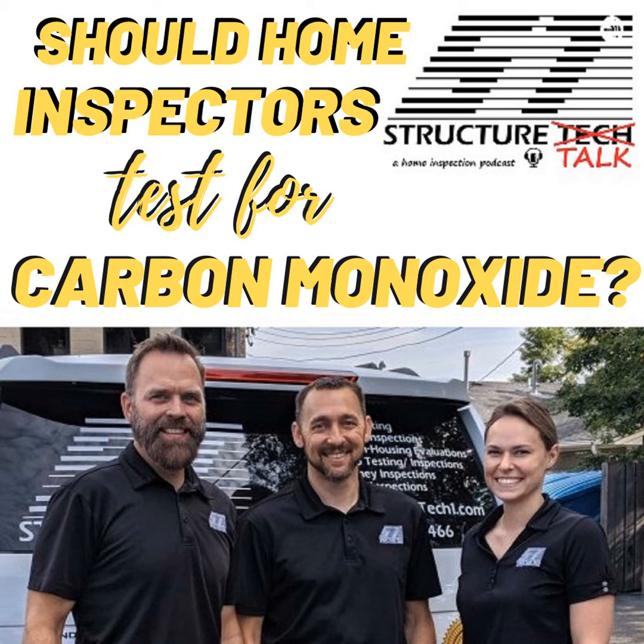So appreciate it. Yes. Another thing that can get confusing for inspectors is where you do the test. And again, it depends on the type of furnace. I think one type that usually throws inspectors is where you test a natural draft furnace. Yes. And you're talking about a furnace that doesn't have a draft inducer fan. They're kind of few and far between these days. There's not a lot of them left out there, but those all have a draft hood, and they are going to have usually between about 2 and 6 ports. And you need to test every one of those ports.